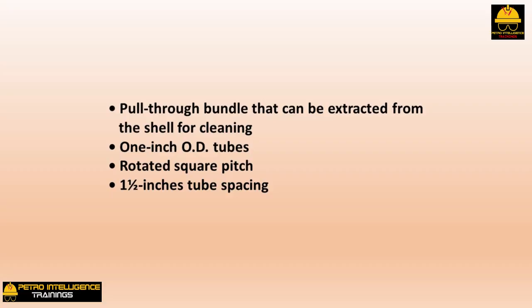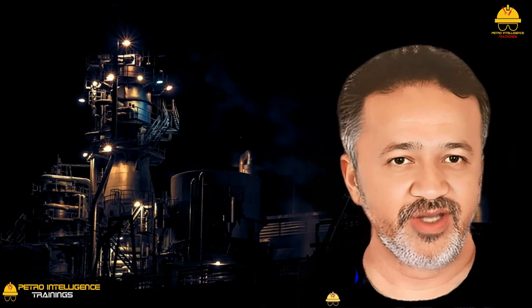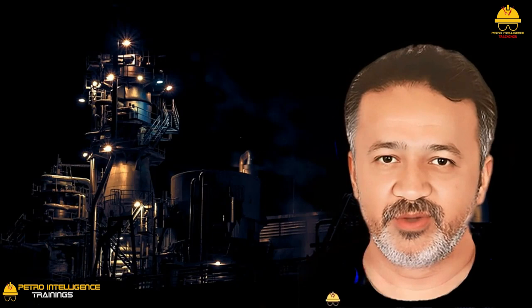The client was not pleased with the cleaning result. The correct design for this service is: a pull-through bundle that can be extracted from the shell for cleaning; 1-inch outer diameter tubes; rotated square pitch; 1.5-inch tube spacing. A fixed tube-sheet exchanger in a refinery pre-condenser service for a vacuum tower is essentially a throwaway item. One operator's replacement for a 60-inch ID shell to the above specifications was $1,300,000 in 2013 — not a happy situation.